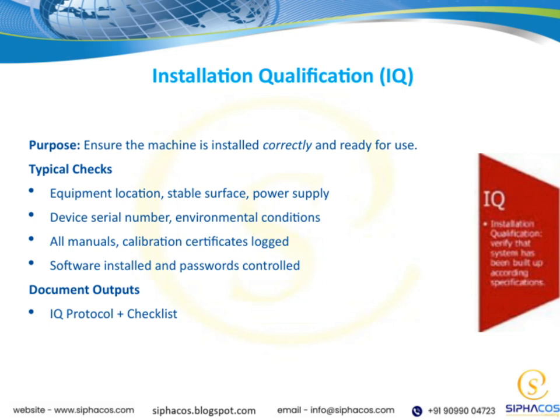We also need to confirm that the power supply is appropriate and reliable. Another key point is to check the device's serial number and make sure all environmental conditions, like temperature and humidity, are within specified ranges. It's also important to log all manuals and calibration certificates related to the equipment. This documentation helps us maintain traceability and ensures everything is up to date.